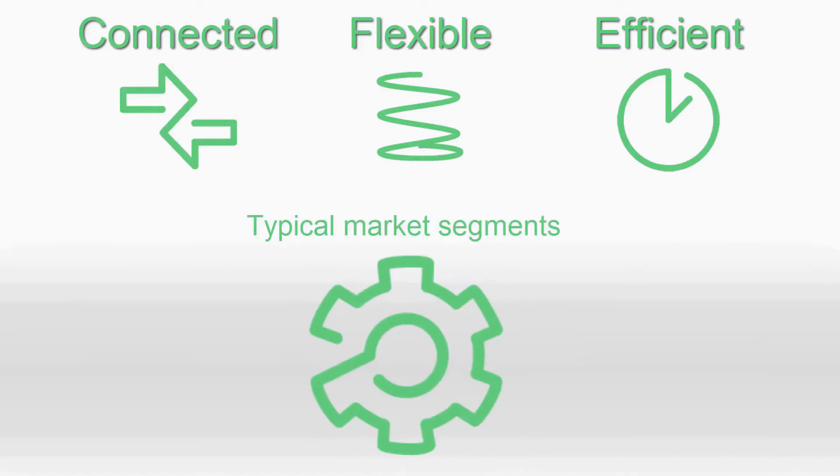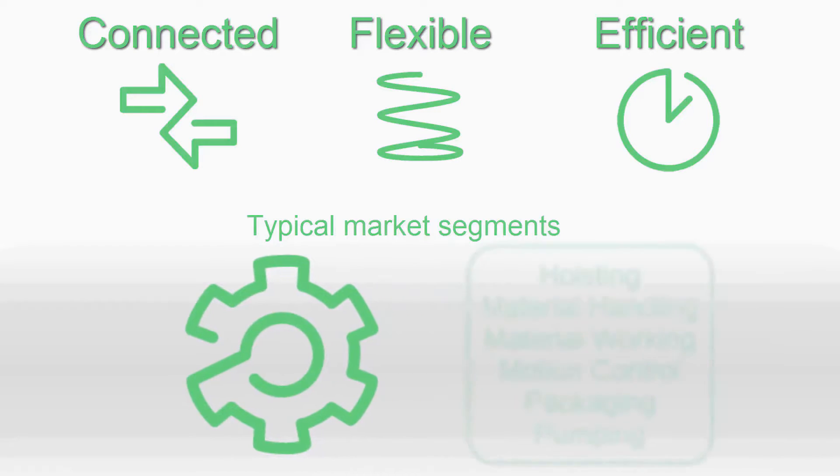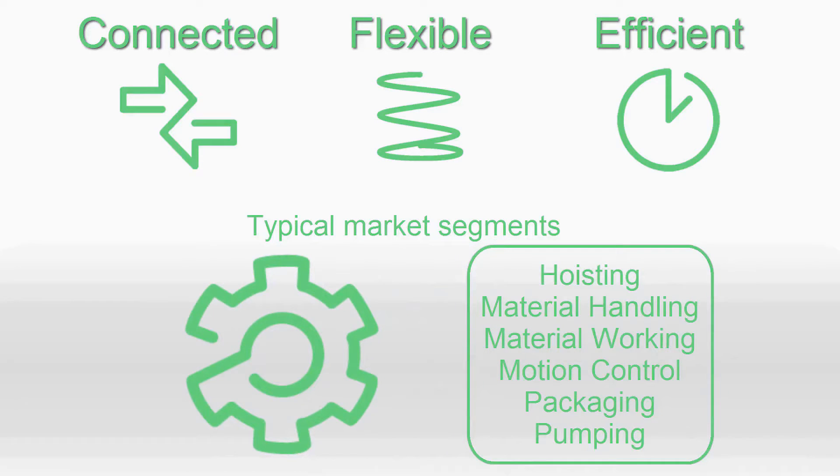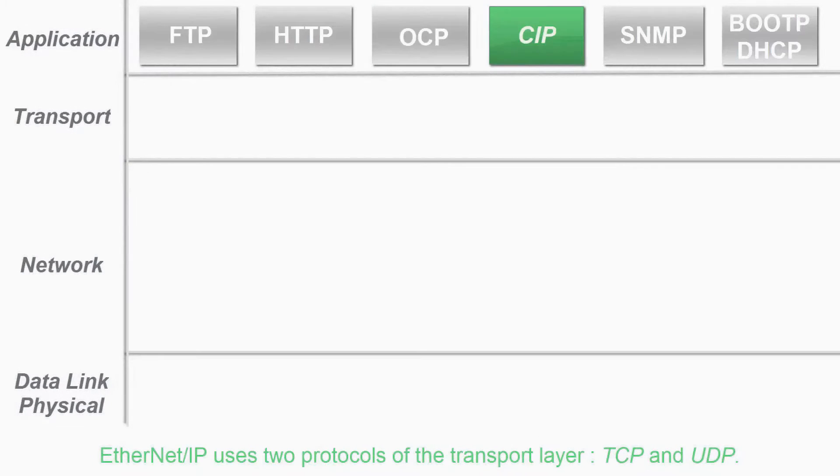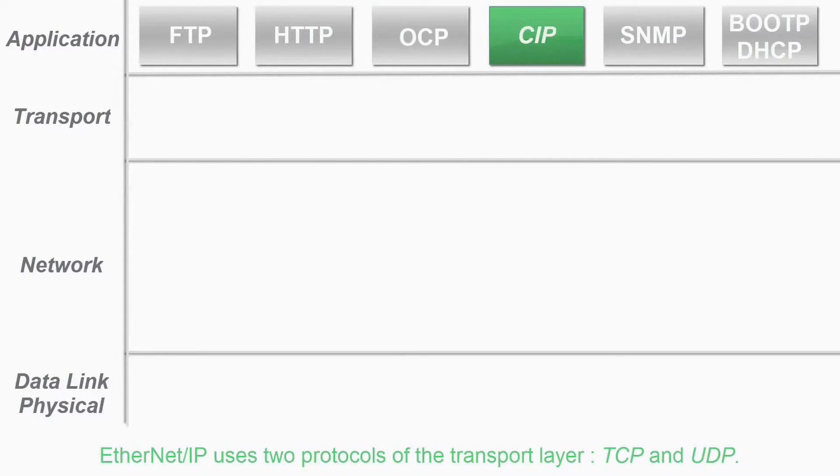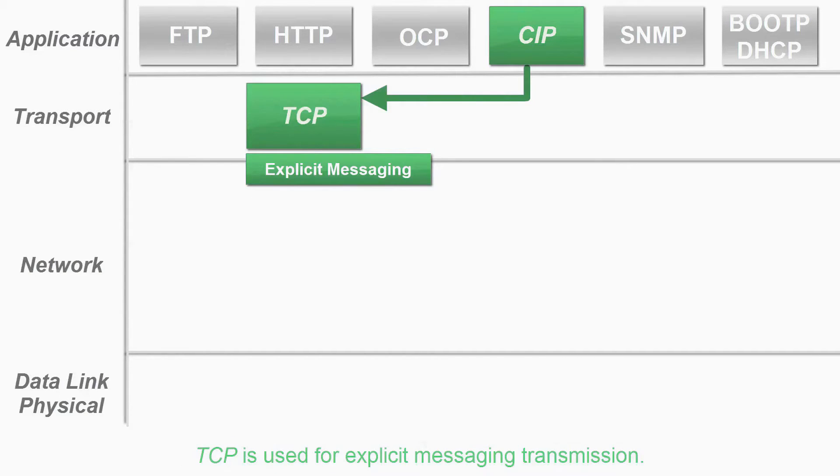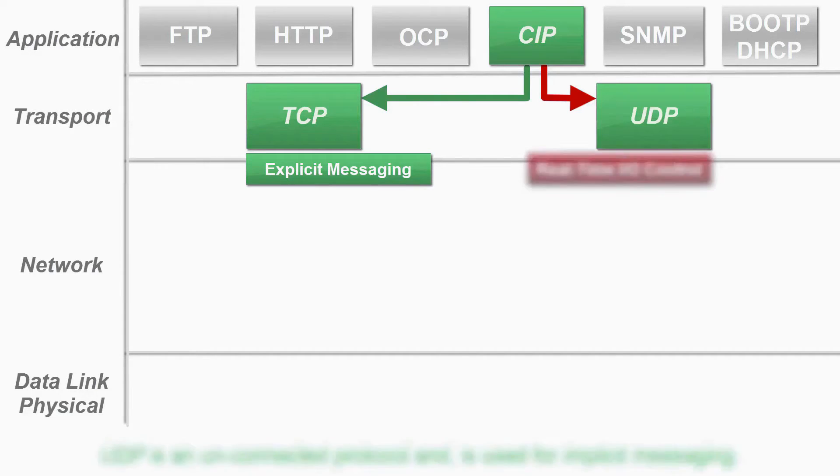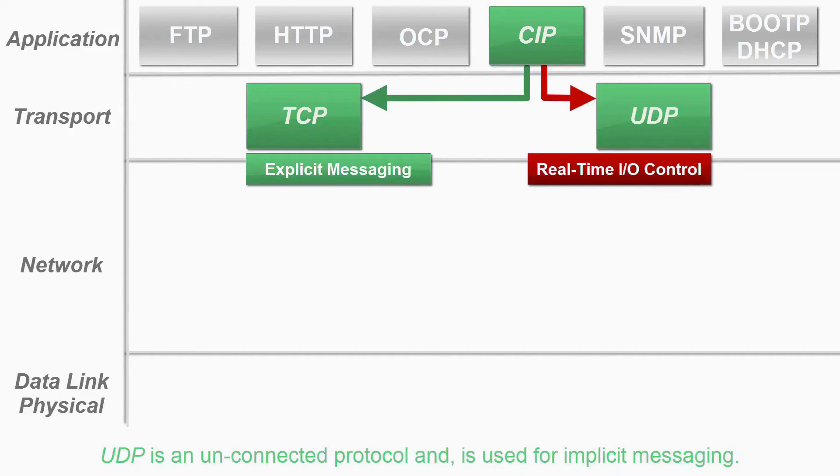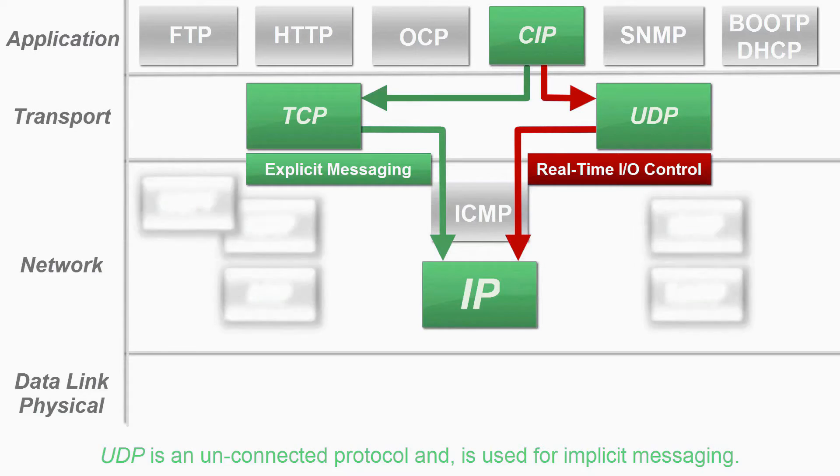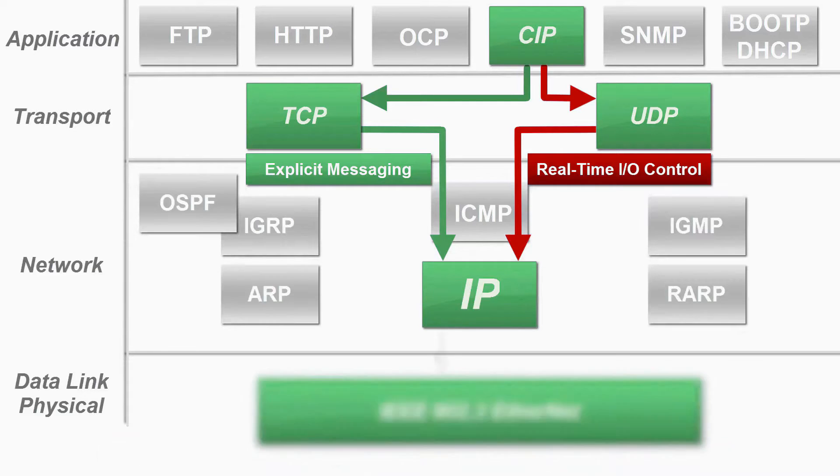With SoMachine you can use the Ethernet IP in several market segments. Ethernet IP uses two protocols of the transport layer: TCP and UDP. TCP is used for explicit messaging transmission. The UDP protocol is an unconnected protocol and is used for implicit messaging.